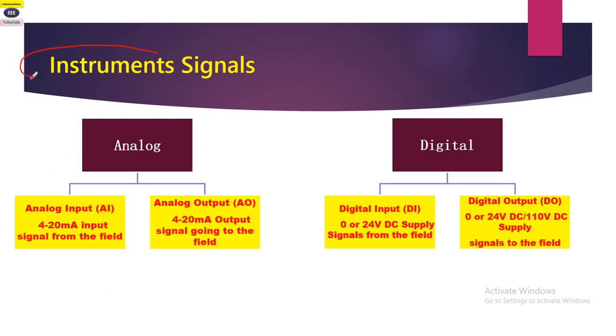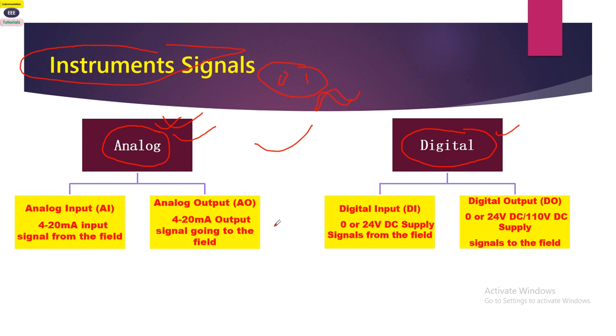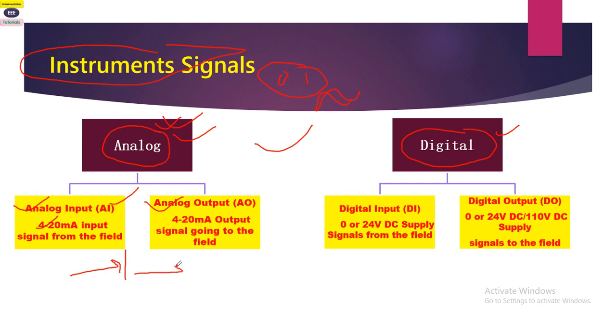Now the instrument signal types: as you may have studied, there are two types of signals — analog and digital. Analog is continuous in nature, and digital is zero or one. Analog also has two subtypes: analog input, which may be a 4 to 20 milliampere signal coming from the field to the PLC, and analog output, which is a 4 to 20 milliampere signal going from the PLC to the field.